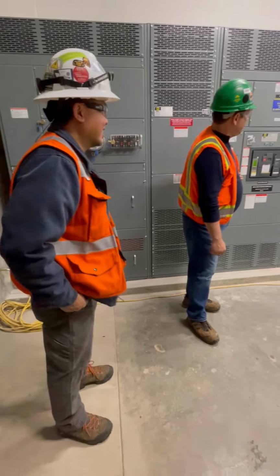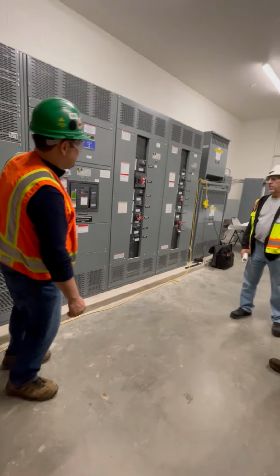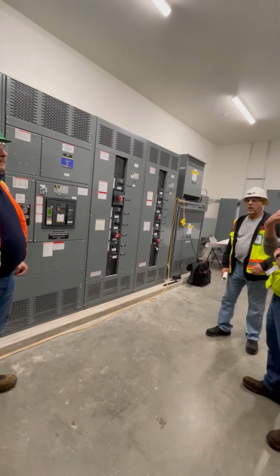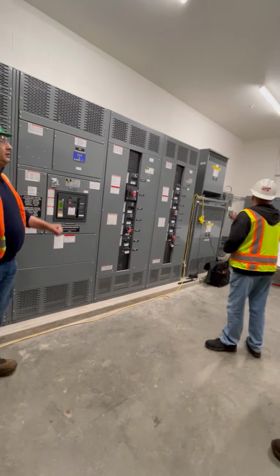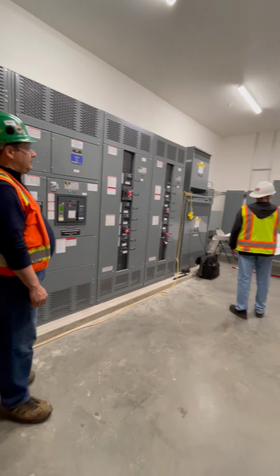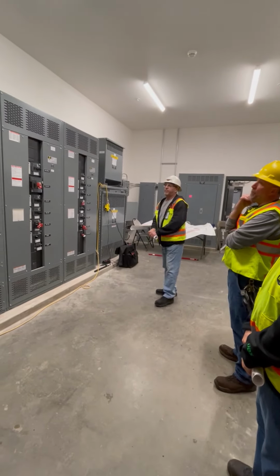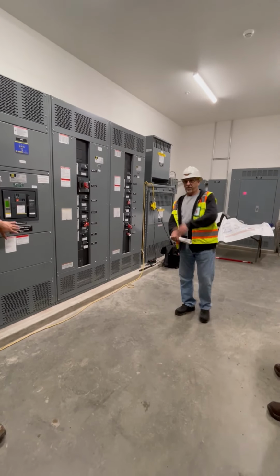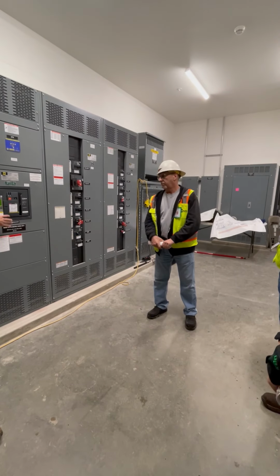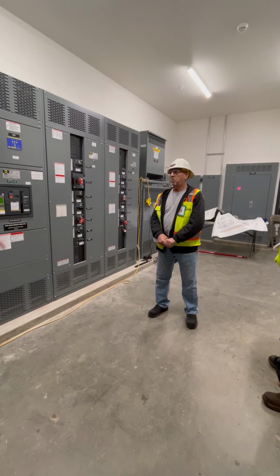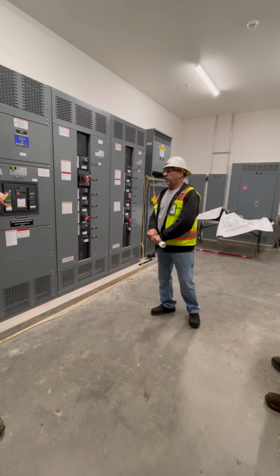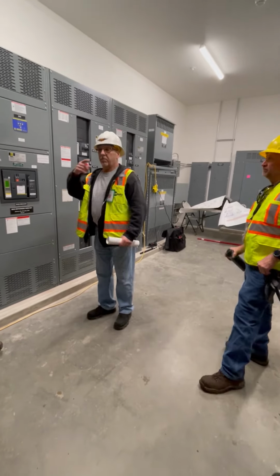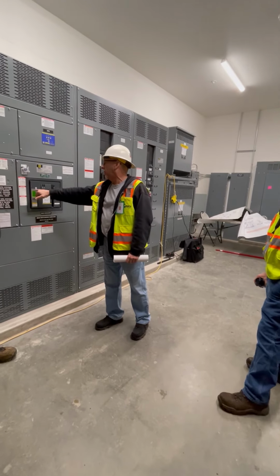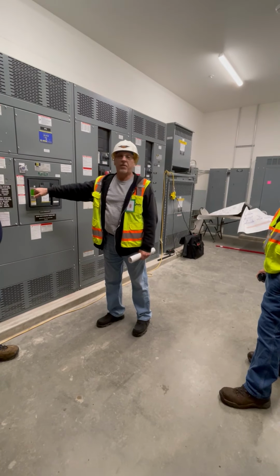But do you have a generator backfeeding it? I don't see one. You say you have an ATS. Not backfeeding this, you have a generator that backfeeds the emergency panel. Ah, so you've got an ATS downstream. That's downstream. Yeah. So you don't have to worry about the generator tripping this one. Again, these LEDs are good because, like you said, it'll tell you ground fault, so then you know how to proceed from there.